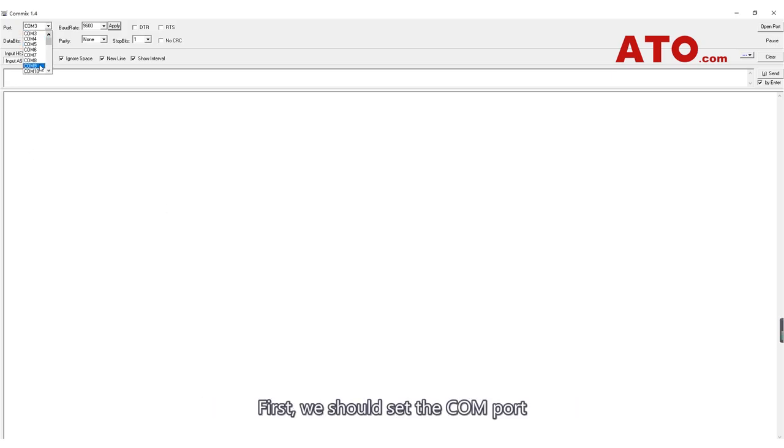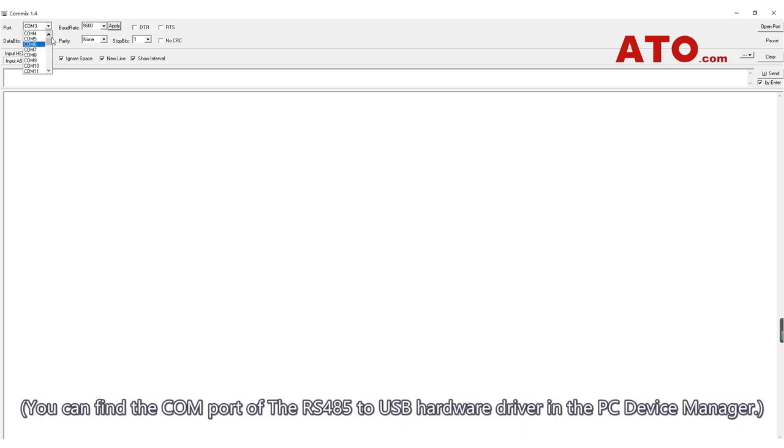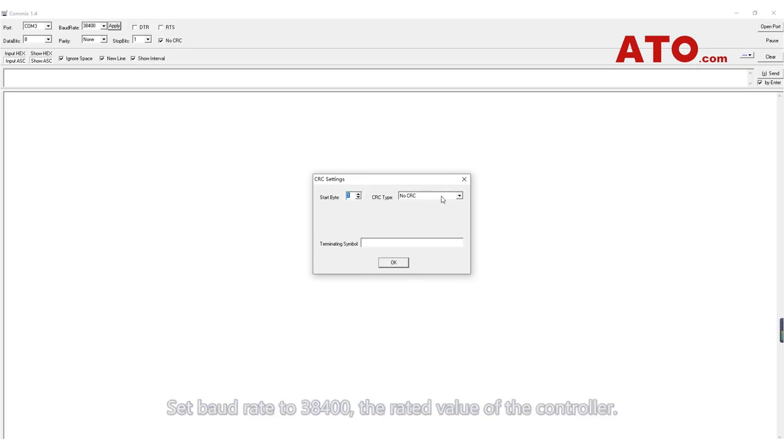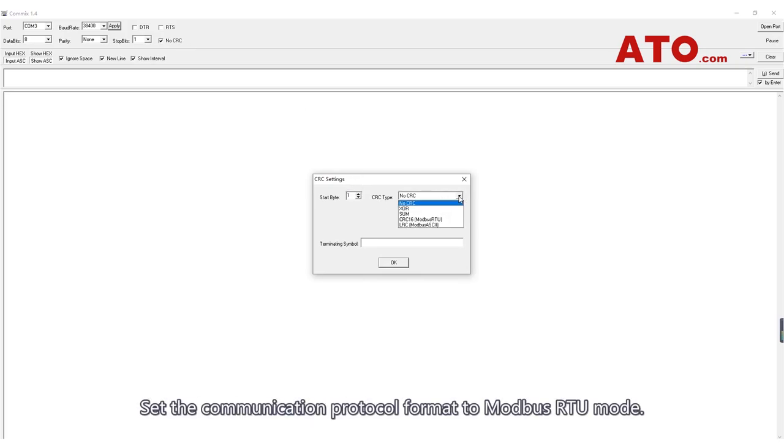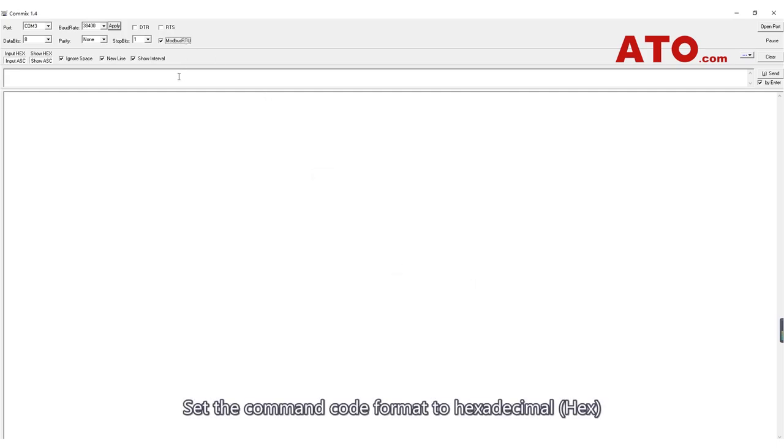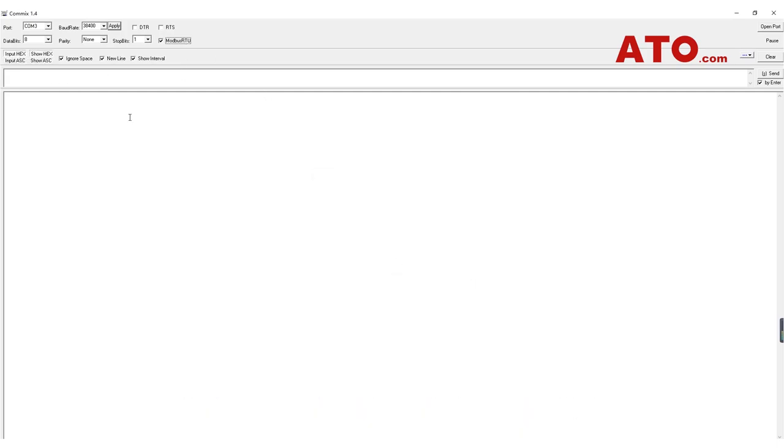First, we should set the COM port. You can find the COM port of the RS485 to USB hardware driver in the PC device manager. Set baud rate to 38,400, the rated value of the controller. Set the communication protocol format to Modbus RTU mode. Set the command code format to hexadecimal. Open serial communication.